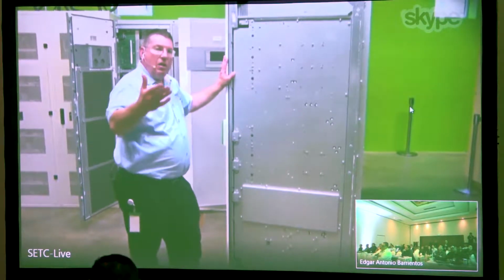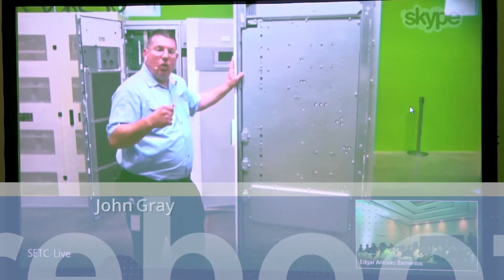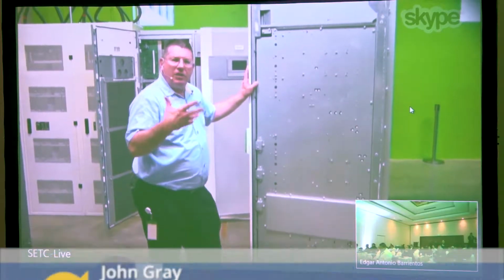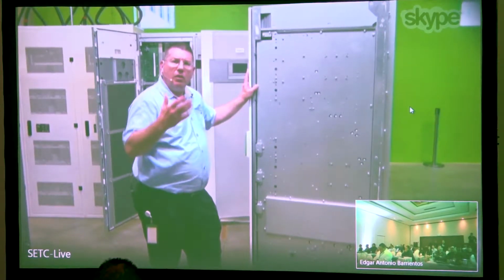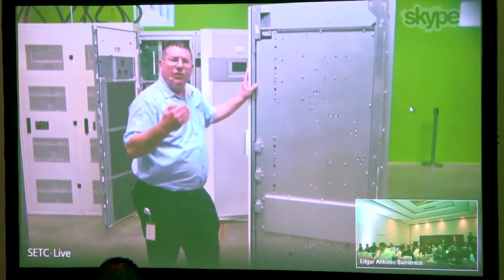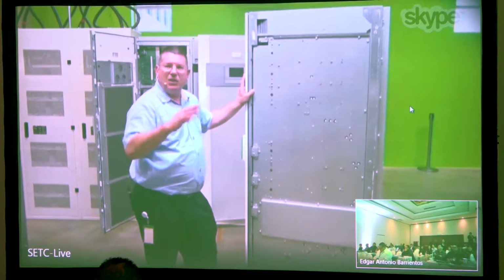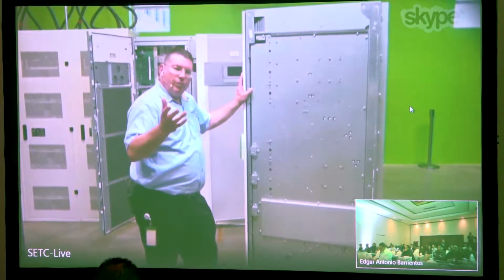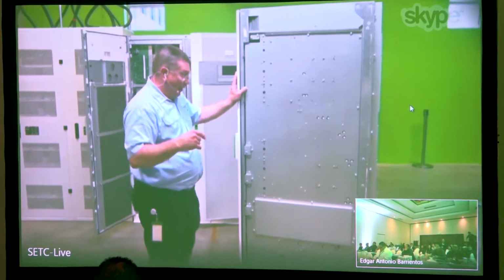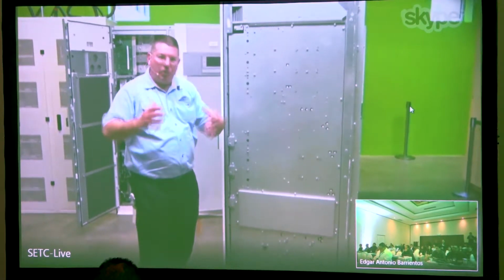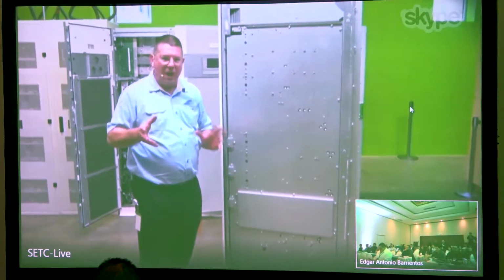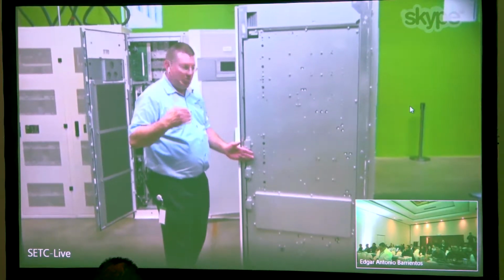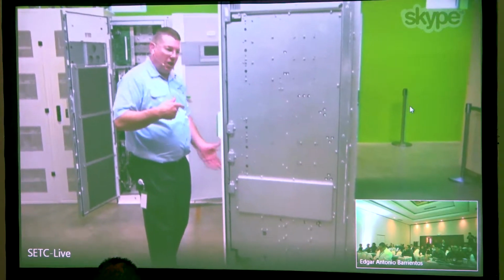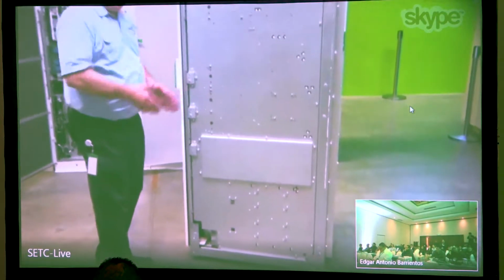So for example, say the data center owner decided that they want to start at 500 kW, but think that they'll maybe go to 1,000 kW in the future, but want to preserve that capital and spend it when they need it instead of spending it all up front. So we can do that just by making sure the input-output cabinet and all the cabling and breakering is sized for that maximum capacity. And then when that time and that decision is made, we can just ship another power cabinet in, and we basically just set down the brackets and roll it into place.